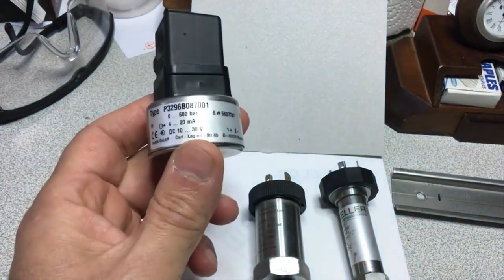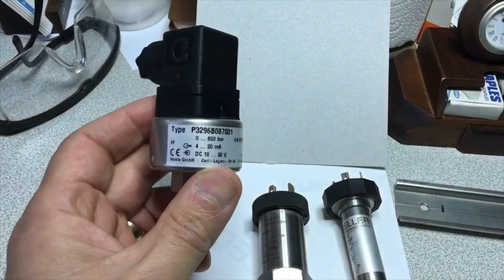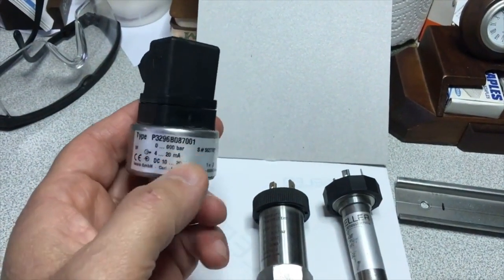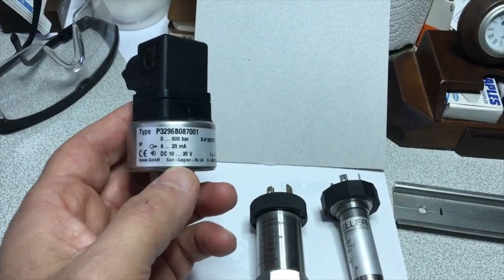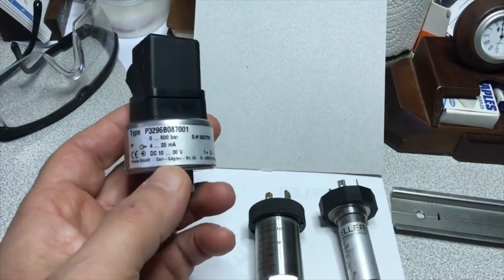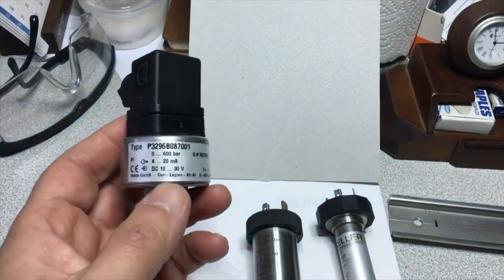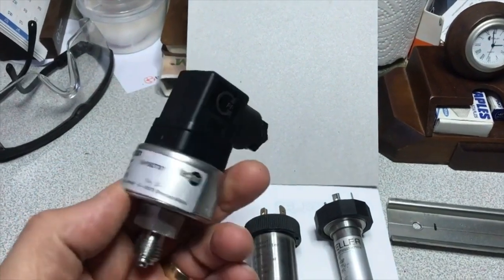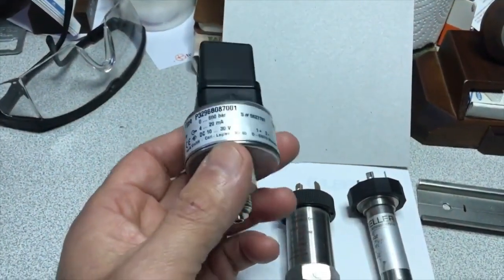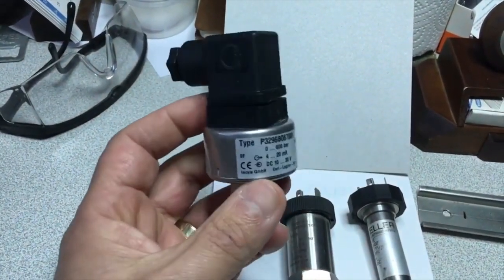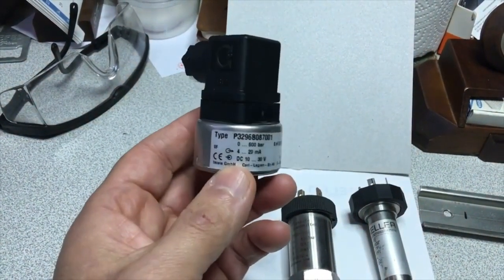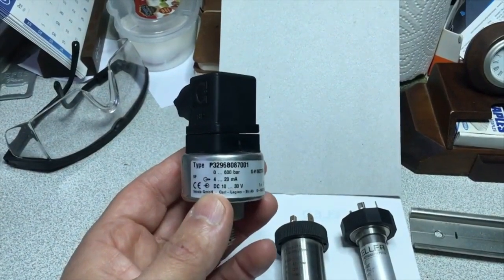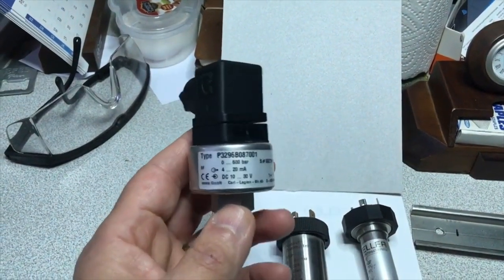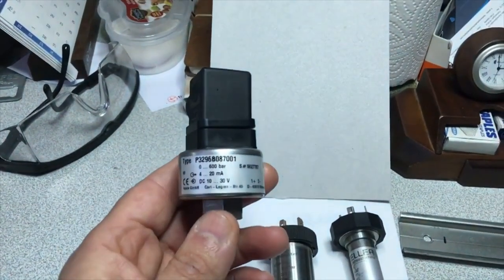Let's examine a newly purchased sensor that has not been used in my hand. It appears to be high pressure in the sense that it can measure pressures between 0 to 600 bars, that is, suitable for hydraulic systems. If it was pneumatic, the upper limit would be lower. Apart from that, it is written that the output current is 4 to 20 milliamperes. The supply voltage is seen to be between 10 to 30 volts. As you know, since we usually use 24-volt DC supply in industrial automation, it meets these limits and stays between the limits.